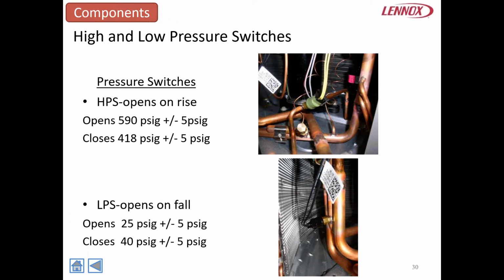All right, so the next thing I want to really touch base on, and this is something that goes across our product line, okay? We have high pressure and low pressure switches in just everything that we've got. And I want to make note of that because I think it's very important. We've talked about both expansion valves, indoor and outdoor, and the importance of pulling a vacuum and ensuring that we use filter dryers and things like that to ensure the system is dehydrated properly, and then also that we take the proper precautions to ensure that it's clean. There is absolutely nowhere for the contaminants to go but right to the screen or right to the TXV. So if you have contaminants in the system, it's going to flow right to that.